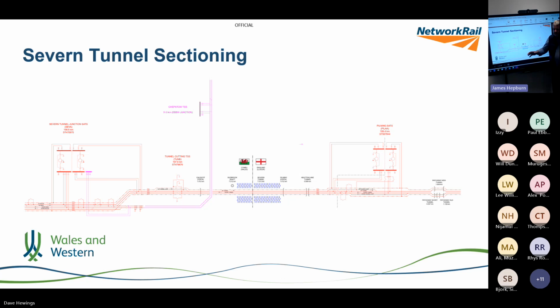What this shows is part of the auto-transformer feeder system that runs the full length of the Great Western electrification - 50 kV distribution, 25 kV supply to the trains, all the way from Paddington through to Cardiff. There are just a handful of grid connections and feeder stations to do that, with substantial capacity. It's got the greatest capacity margin of any part of the electrified network.